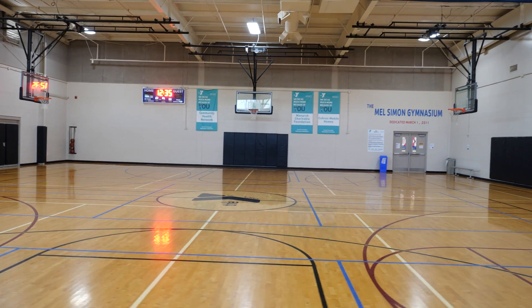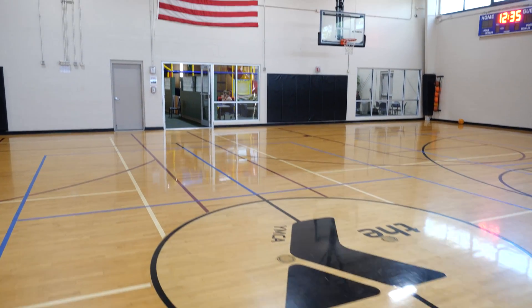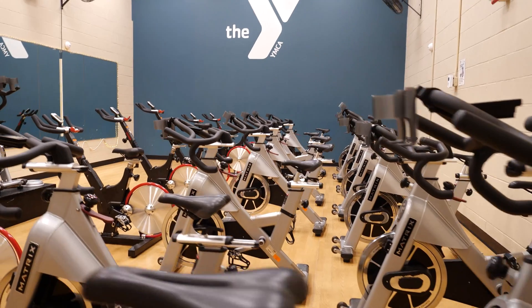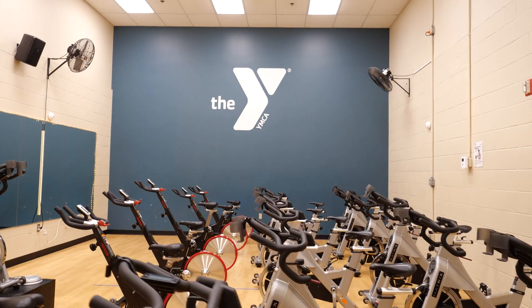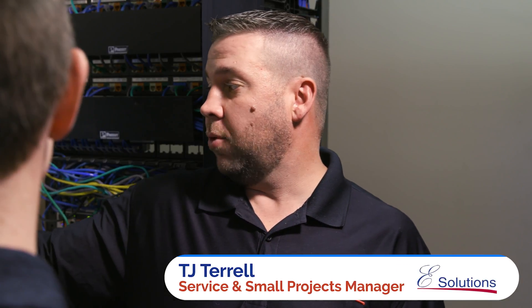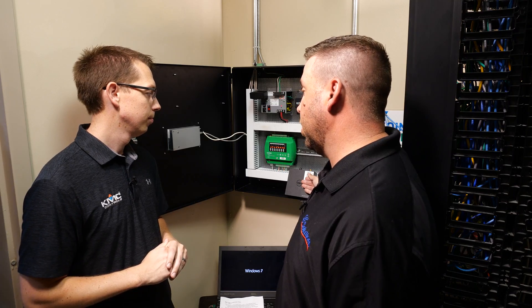TJ, tell us a little bit about the system that's already on site and how we're going to be hooking up Commander into it. Currently the YMCA here is about 56,000 square feet. We have approximately 14 single zone rooftop systems here, currently running on our main platform of Tridium running KMC. We are going to implement and start using the KMC Commander moving forward for ease of access. We are currently going to use the BACnet points using the KMC router to pull in the points into the Commander.